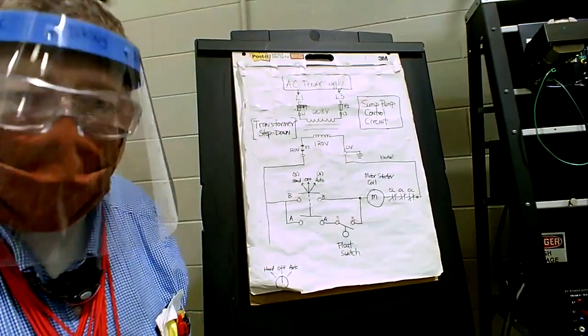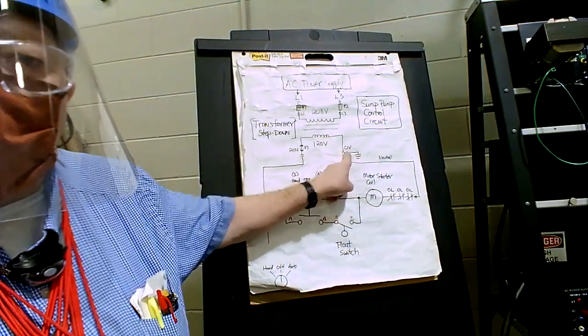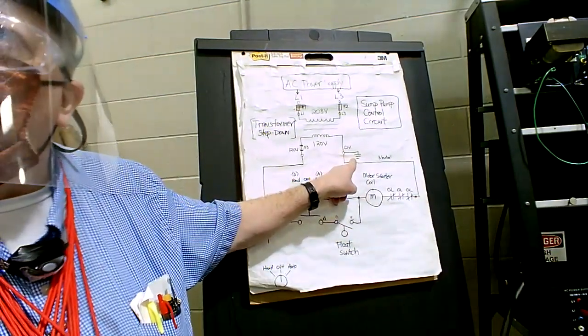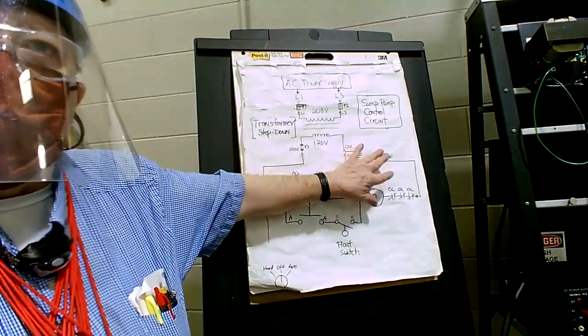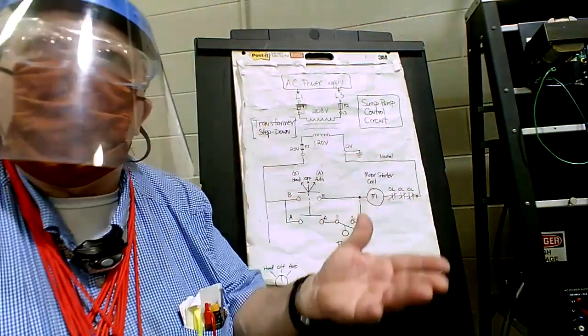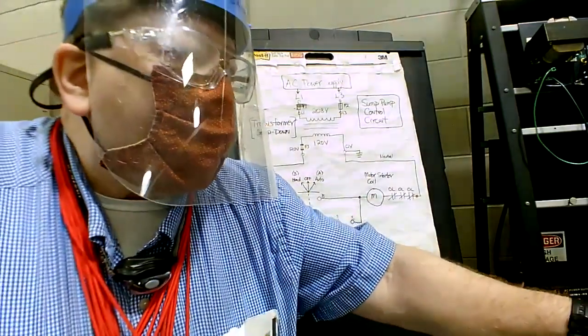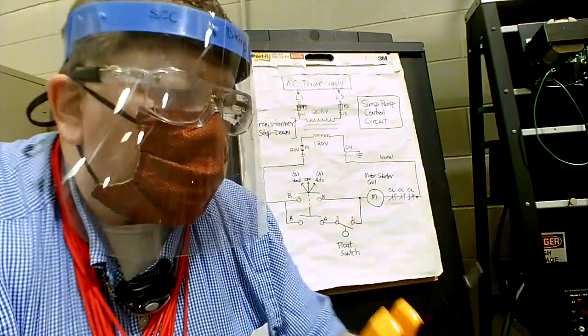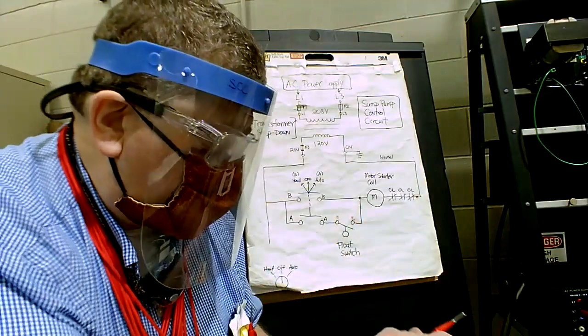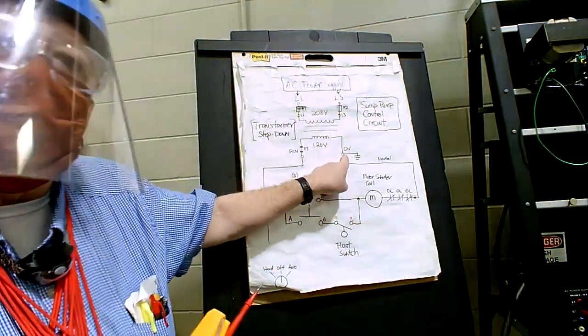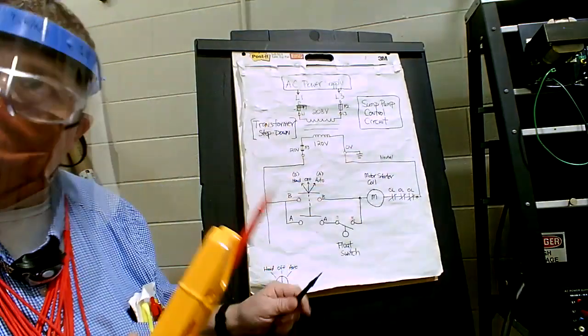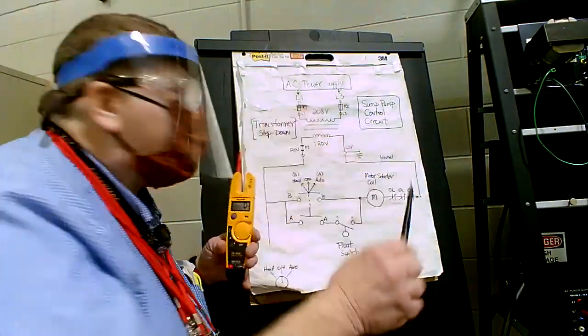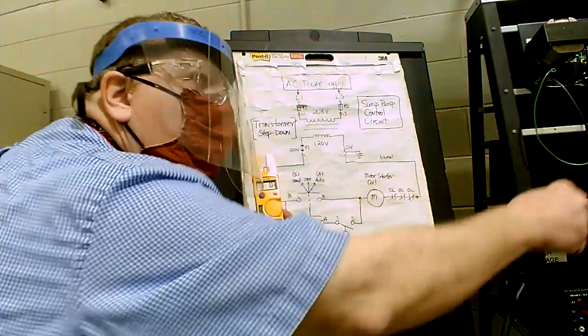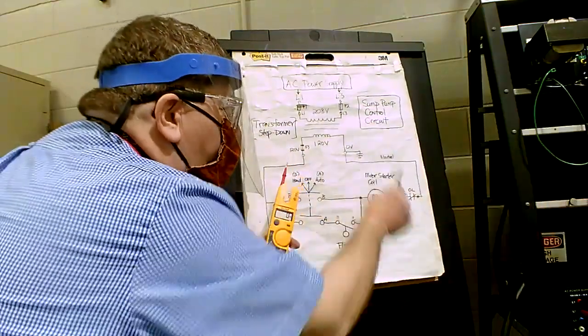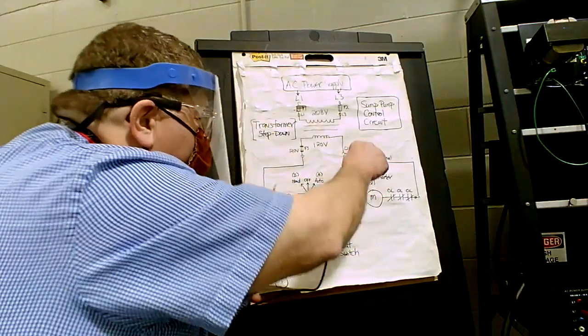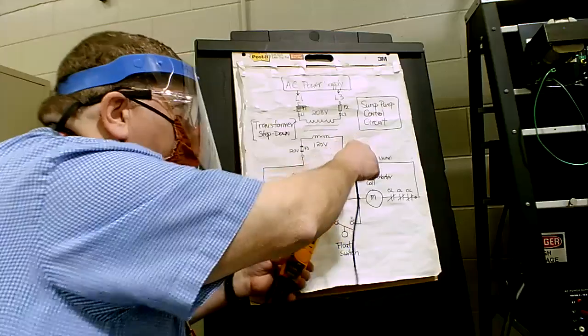So those of you, Taekwon and Zach, if you're out there watching this, normally we do ground the secondary neutral wire coming back. That's what's most common in the industry, and it's considered a grounded secondary. Now, when you do that, here's the way you properly test for voltage. Let's see the meter here. The book tells you that if you ground that secondary, when you go to troubleshoot the circuit, you can go to any grounded point in that circuit, any ground on that control panel, that ground or any other ground, and then test. If I go to that ground, I can trace my signal out, and I will get an accurate reading on the meter.